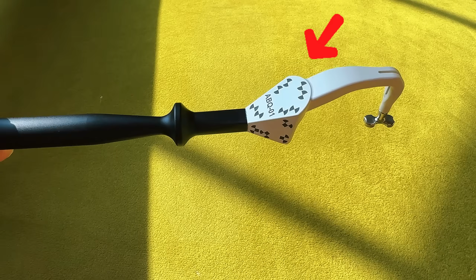Registering this new probe in the software is quick and easy. Simply open the MicronMapper application, click on More, then select Register New Tissue Mapper Pointer. Look at the pointer and locate the series and opticode number. Enter both values into the software and click Download and Register. Your tissue mapper is now added to the software.